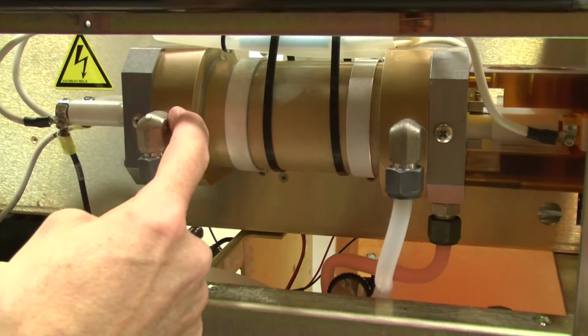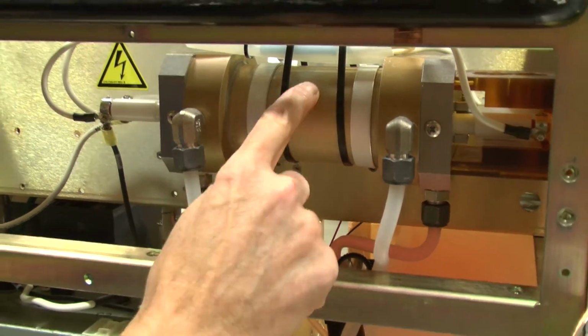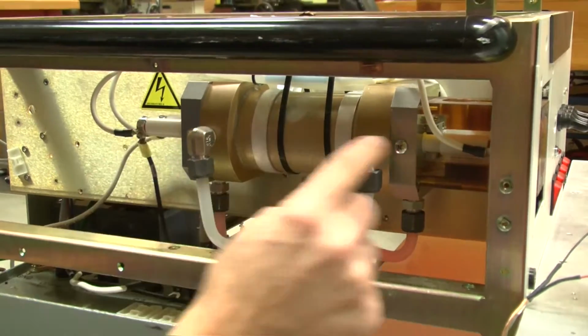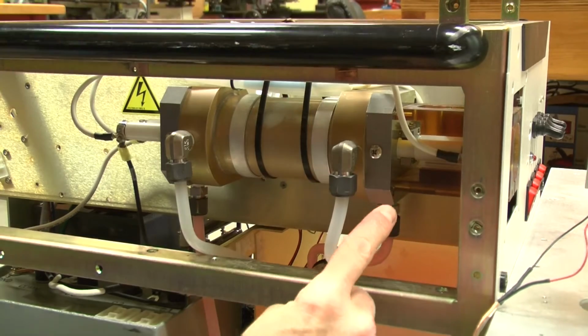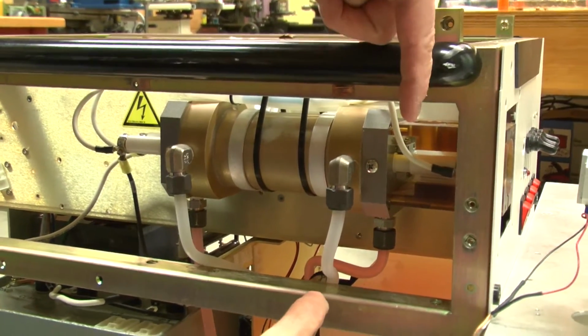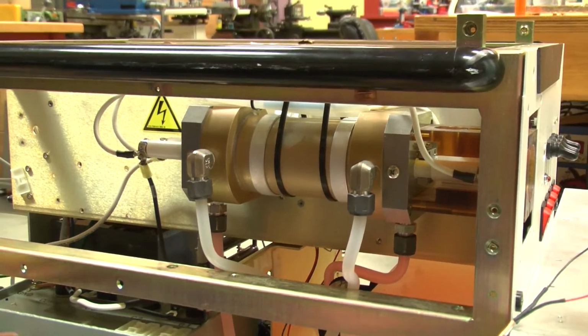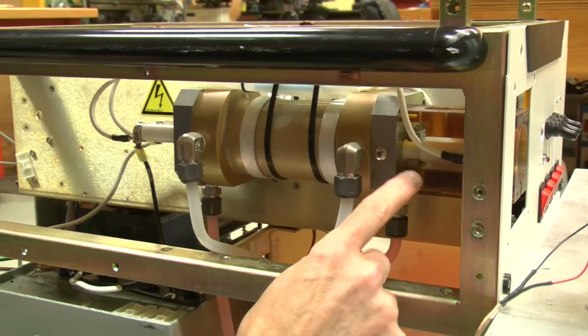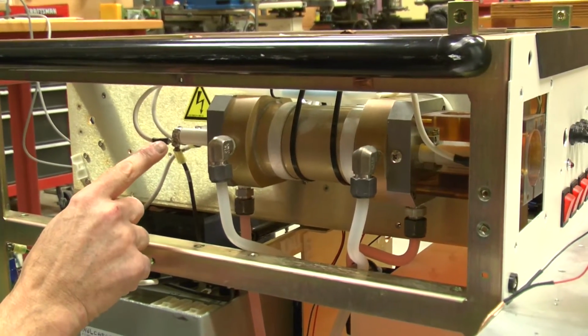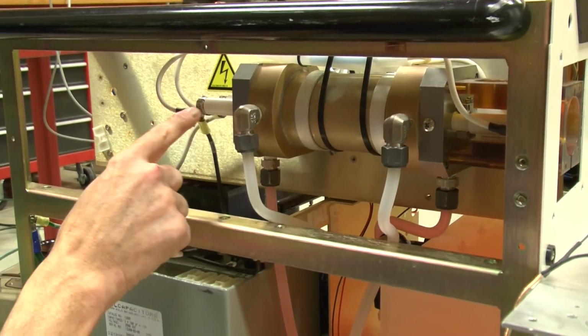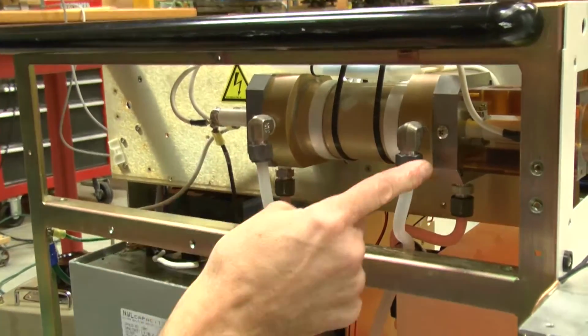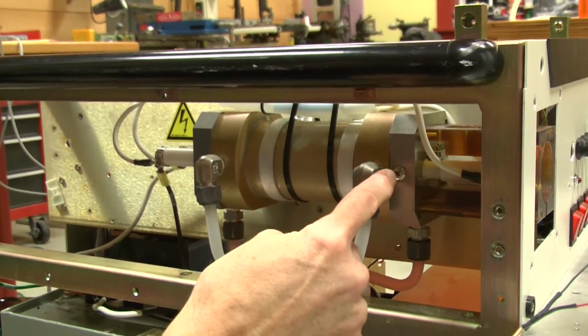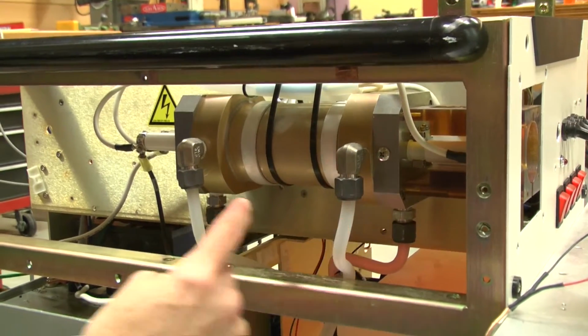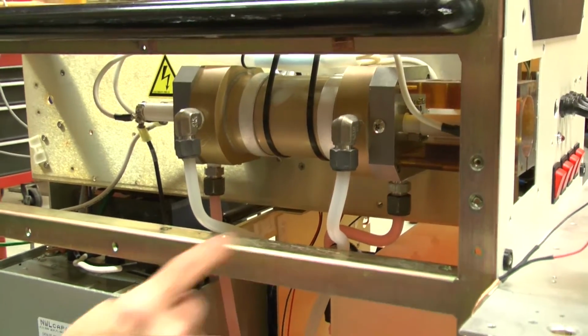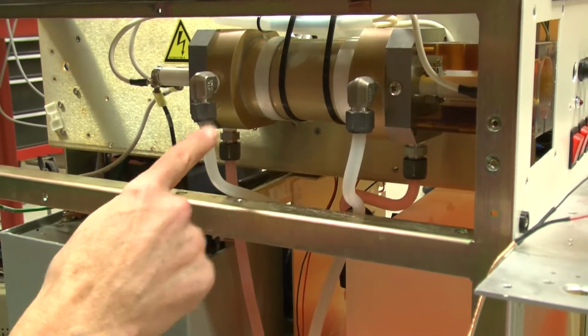These are the cooling tubes for the flash lamps. And effectively, because they're going through the metal components, they cool the outside jacket that has reflective material on the inside of it. The two parallel flash lamps are pumped in a U-shaped circuit. So pump energy goes in one side, bridges across through a wire, comes back, and then grounds back down to the capacitor. The unusual thing with these lamps is that the studs that come out of the ends of them are actually stainless steel studs about 2 inches long, and they are actually wet. The DI water not only contacts the outer jacket of the quartz tube, but actually touches the metal, and that's why it has to be DI water with a very high resistance, so that the high electrical energy doesn't just transmit right through the water. That's why DI water is important here.